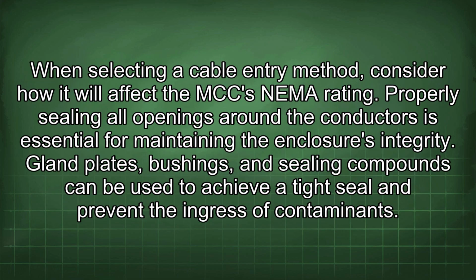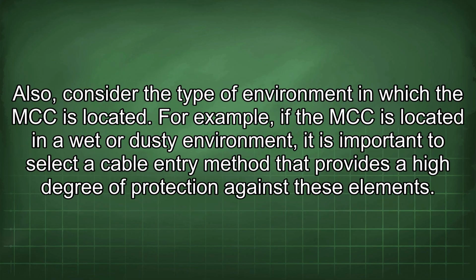When selecting a cable entry method, consider how it will affect the MCC NEMA rating. Properly sealing all openings around the conductors is essential for maintaining the enclosure's integrity. Gland plates, bushings, and sealing compounds can be used to achieve a tight seal and prevent the ingress of contaminants. Also, consider the type of environment in which the MCC is located. For example, if the MCC is located in a wet or dusty environment, it is important to select a cable entry method that provides a high degree of protection against these elements.